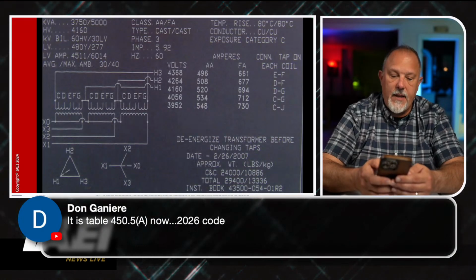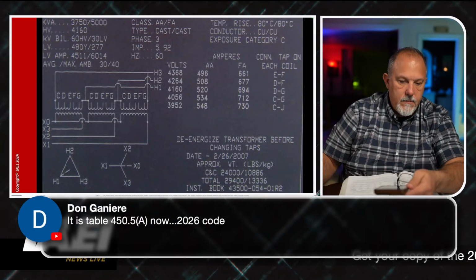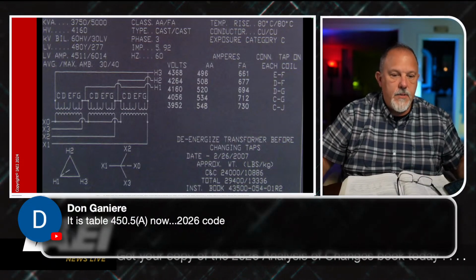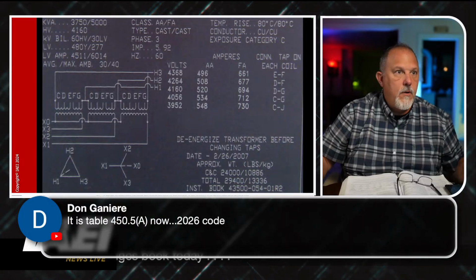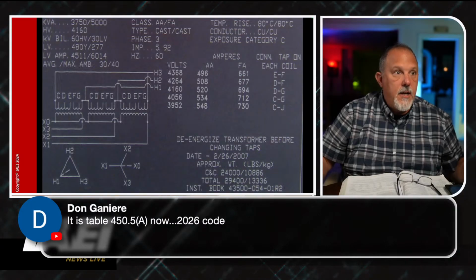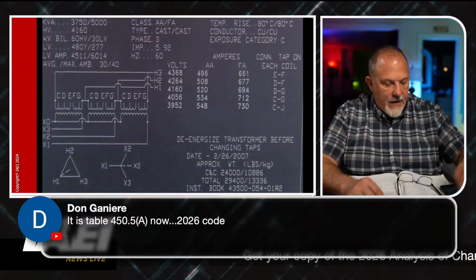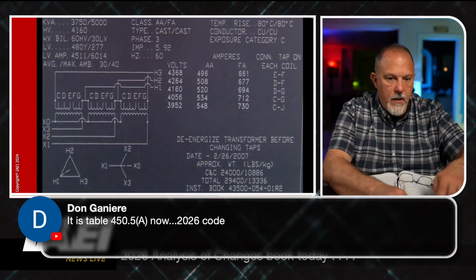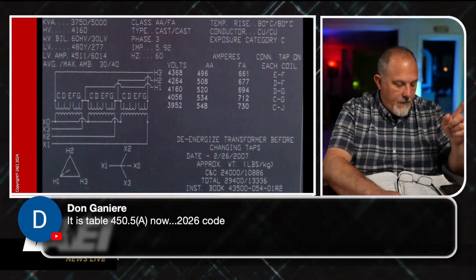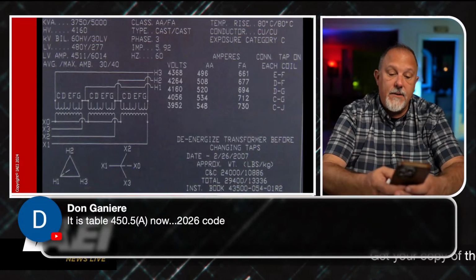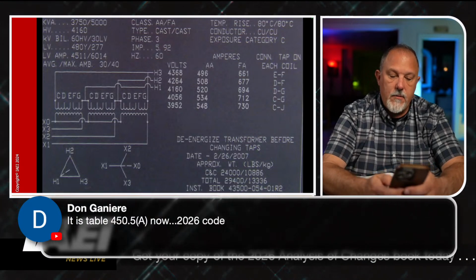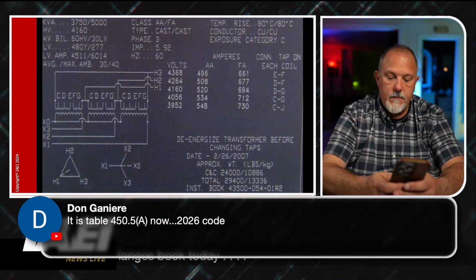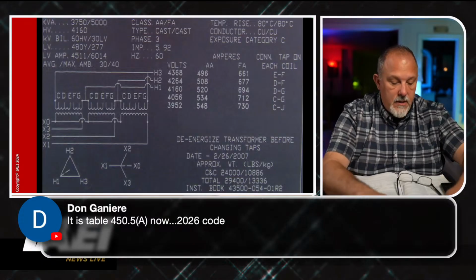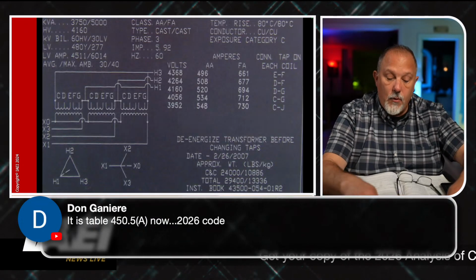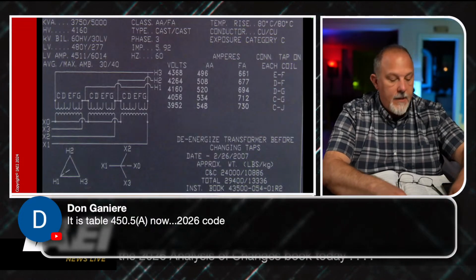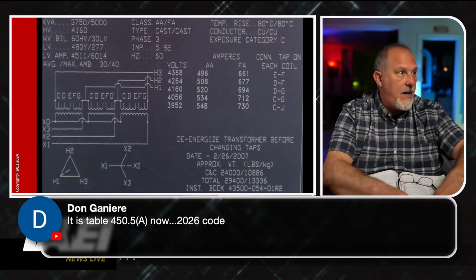All right, so that's at 3750. I've got 520 amps. I need to write this down. 3750, 520 amps. I'm going to move this over here. All right, so 520 amps at 3750 primary. Then if I'm at 5,000, I take 5,000 kVA, divide that by the square root of 3, divide that by 4.16, and that's 693 amps. 694, it's 0.9. 694 amps at 5,000 kVA primary.